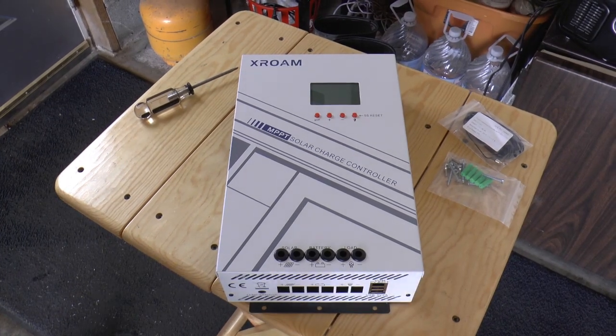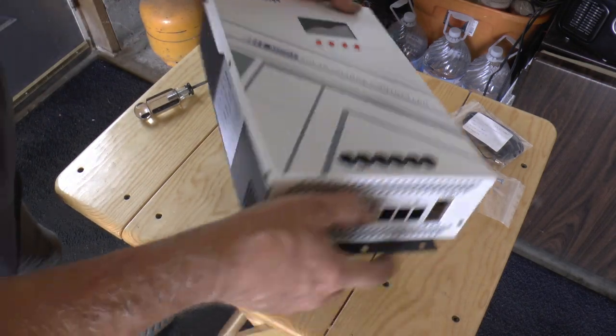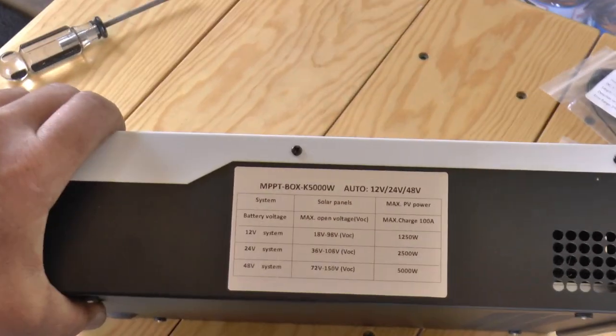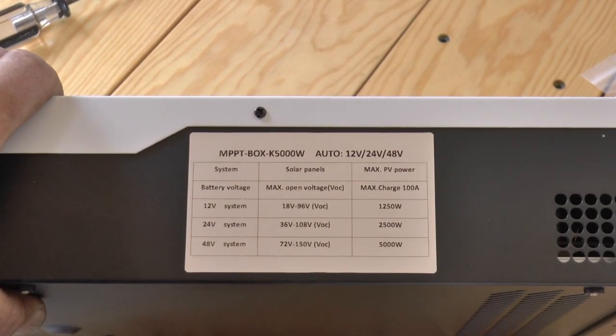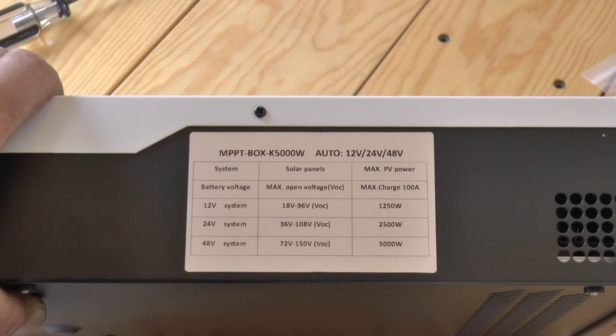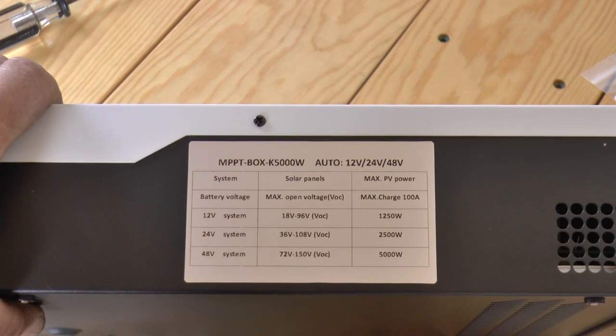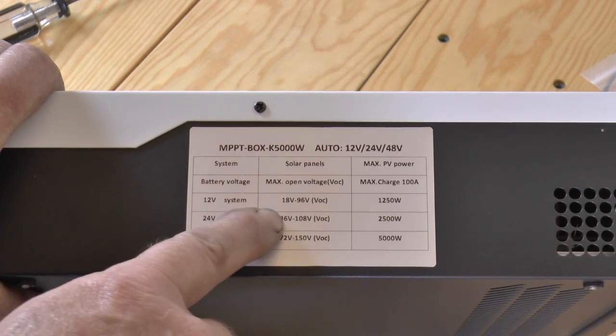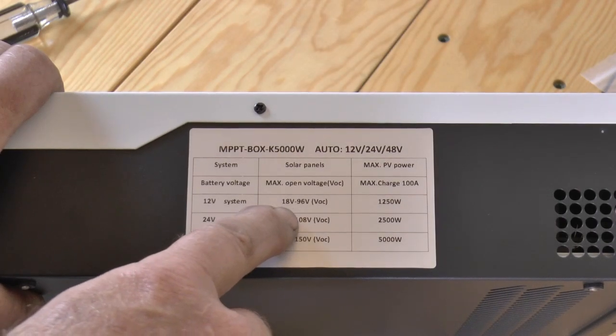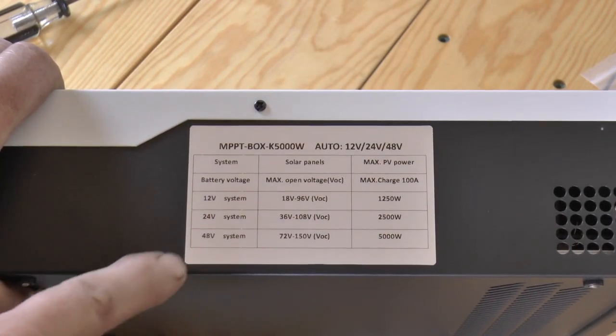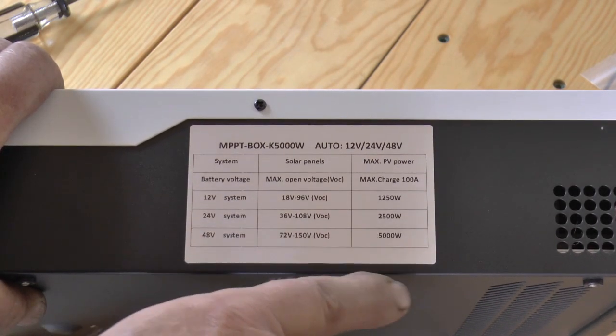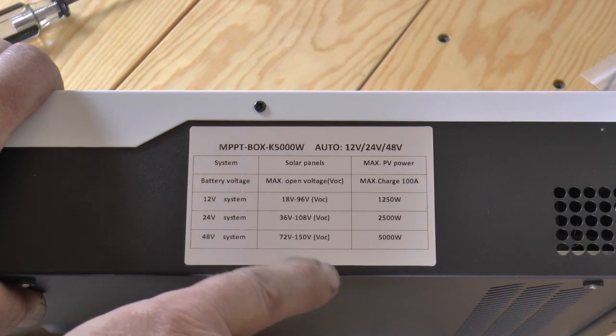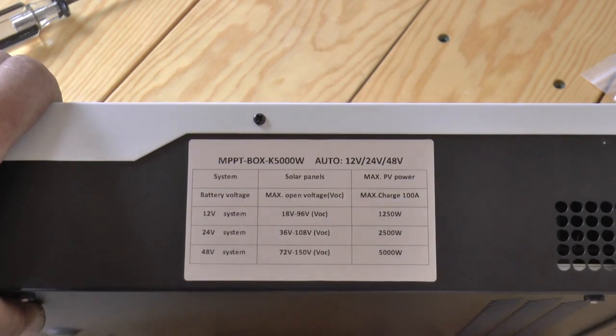I was pretty busy grumbling about the manual, so let me show you the unit itself. On the tag here, this one's the model MPPT-BOX-K5000W and it's auto 12 volt, 24 volt, and 48 volt selection. 12 volt system maximum open circuit voltage is 18 to 96 volts, 1250 watts. 24 volt system 36 to 108 volts, 2500 watts. 48 volt system 72 to 150 volts open circuit, 5000 watts.